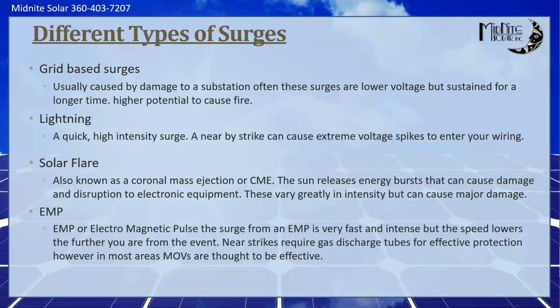Direct strikes are a little tougher, but with the right equipment in the right places, you can be pretty lucky most of the time. I'm not going to sit here and tell you that my product will absolutely 100% stop you from damage during a direct lightning strike, but I'm going to tell you that if you do everything right, you have a high probability of surviving that lightning strike with very minimal to no damage. We'll talk a little bit more about that as we go on, but that is something to be very aware of. Direct lightning strikes are no joke.